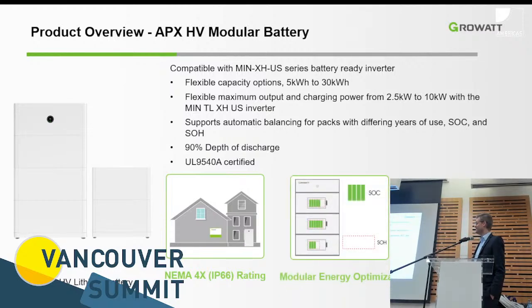It can be installed technically outside. The product, as so many other products, is not specifically developed for the Canadian market, where very low ambient temperatures are the norm. So I would not recommend putting the system outside, because these batteries are not self-heated. For proper operation, specifically on the charging side, you need to make sure that the battery is above 0 degrees. You should not be exposed to freezing temperatures, otherwise the charge current will be extremely slow, and the value proposition for the customer to have a reasonable recharge rate is not there.